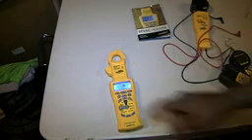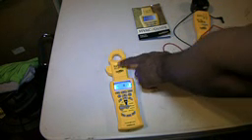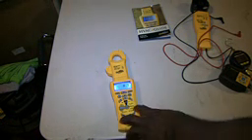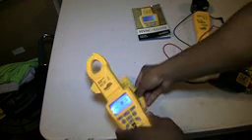And another cool thing, which I'm still trying to figure out by trial and error, is that this thing here can tell you your inrush current. Last night I used the AC clamp head and the HVAC Guide, and I was able to read inrush current. But then when I tried to attach my AC clamp head to a wireless transmitter, I couldn't get the readings that I was looking for.